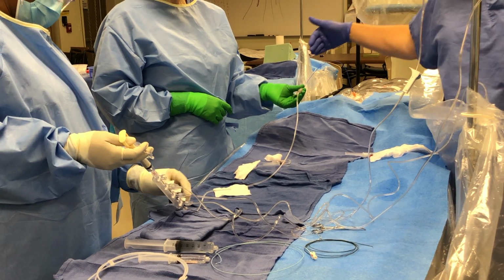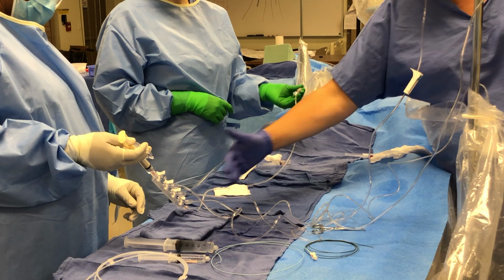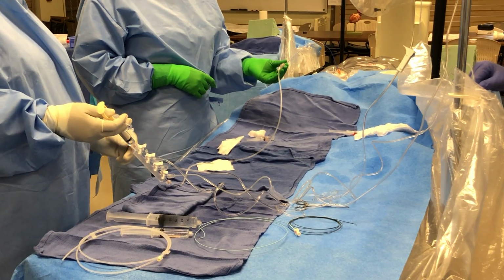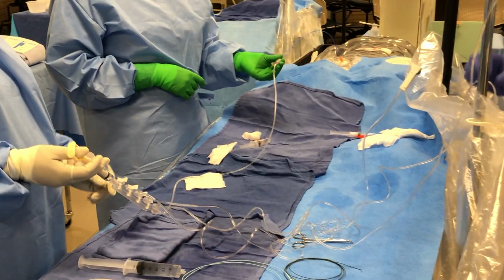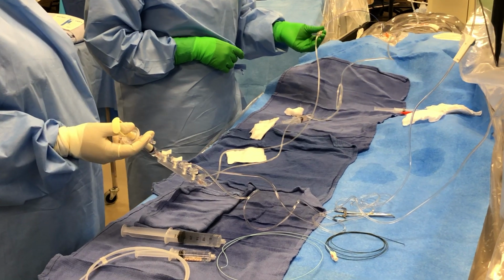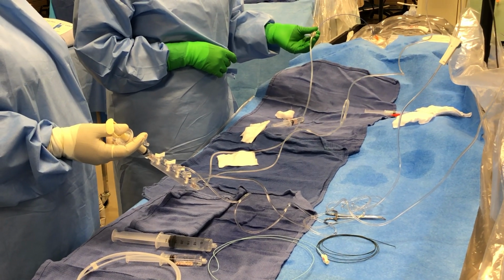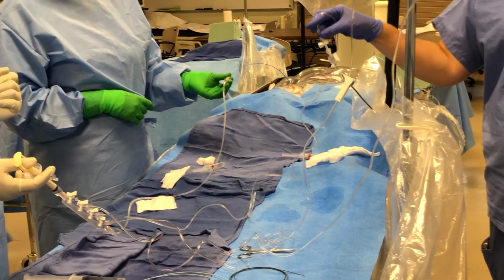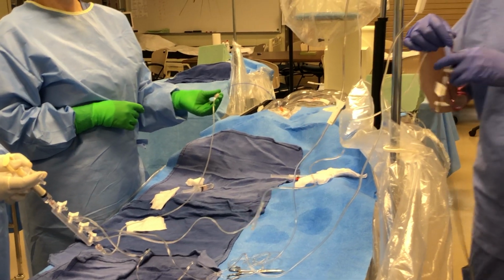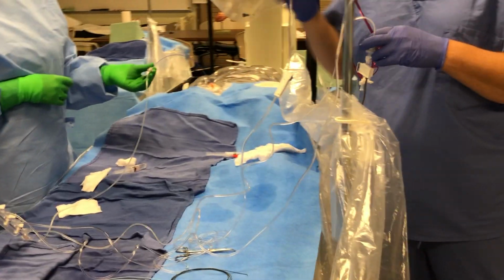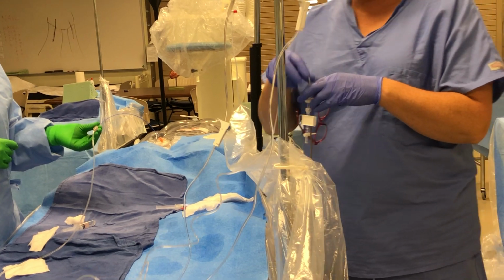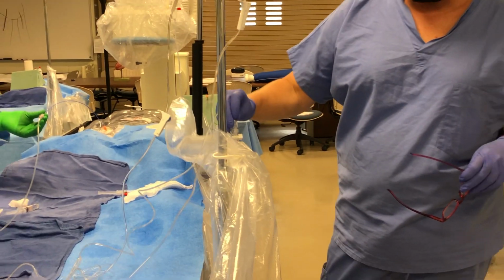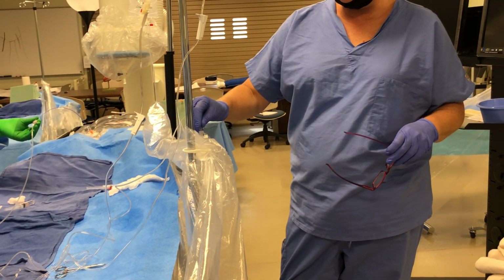So we can read pressure from the patient to the transducer. This transducer should have also been turned open after we've zeroed so that we can, and Amar, you've got to keep that hand up. There you go. It's okay. Just think about that it needs to be at table level. You can't drop it down by your side. Okay?